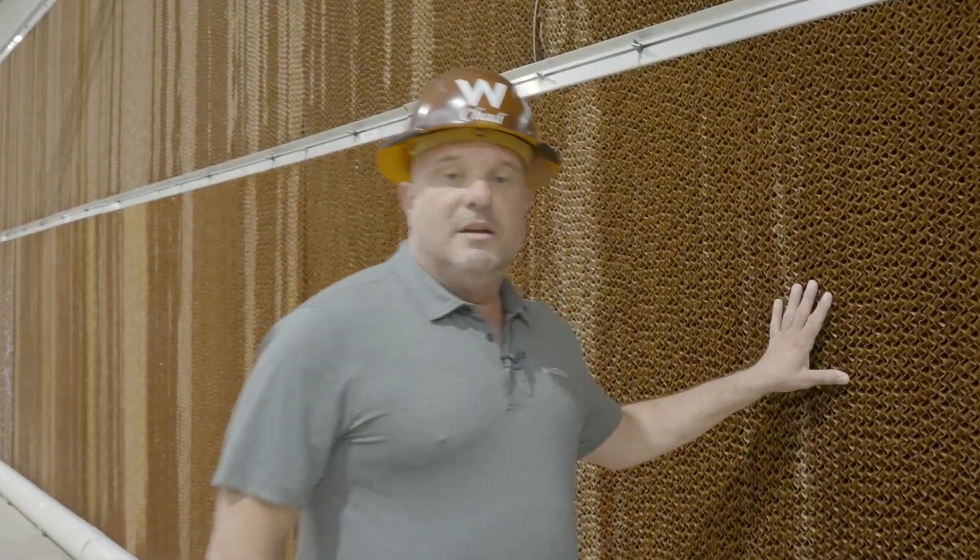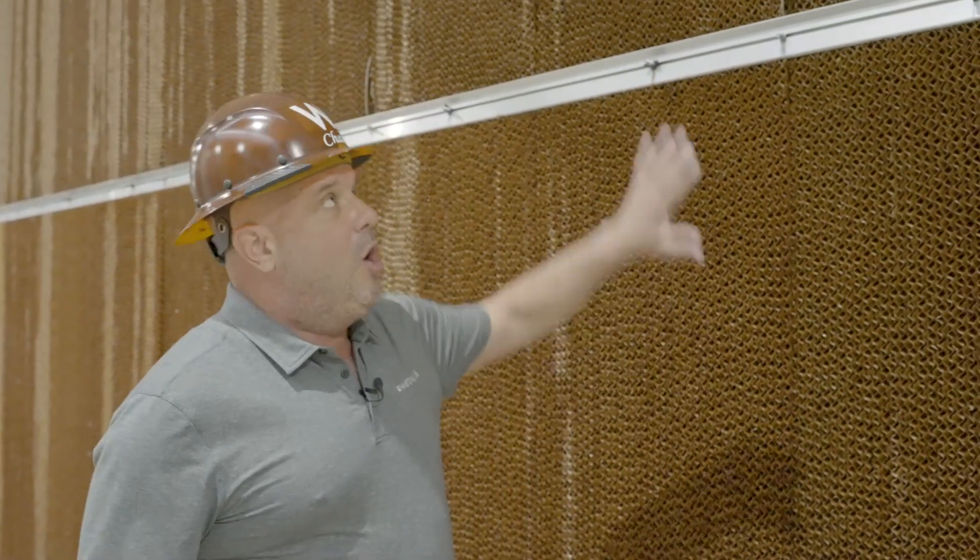We're inside Building B and the miners are humming. Let's walk over to our evaporative cooling wall. Water drains from the top to the bottom and recirculates outside. We collect it in 1,000-gallon tanks stored underground. We have a water loop throughout the property with a 2,000-gallon-per-minute pump. It provides clean, recirculated water, drops our internal temperature, and helps control dust.